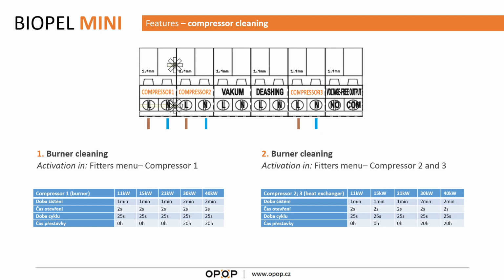Okay, so I think there is no need to change these values. Of course, we always say to the customer, please check the burner, please check the heat exchanger, let's say once a month, to see if everything is clean. If they see more ashes inside the heat exchanger or inside the burner, then of course you can increase the cleaning time here to make the cleaning longer, or you can select here a shorter period of time, so the cleaning will be performed during operation more often. Okay, so this is how the compressor cleaning works.